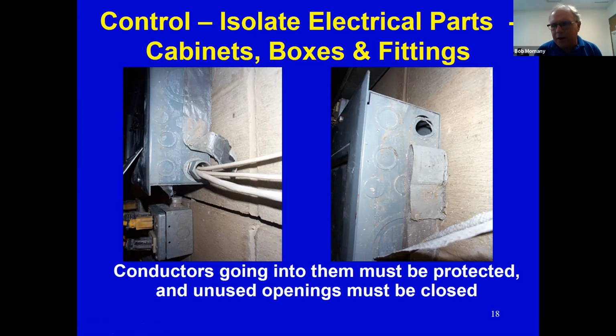But here's a bigger issue that I've run across a couple of times. When that is left open like that, depending on the environment, you could get dust that accumulates in something like that. And then somebody's going to come along and take that cover off that box. If they disturb that dust that may have accumulated in that box and that dust falls and it causes the contact, well, what can happen is you can have an explosion. And somebody, of course, is standing right there in the blast zone when that comes out of that box.